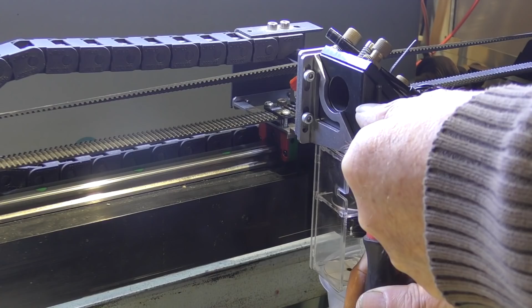Now what we've got to do is move the beam backwards. And how do we do that? Well, the answer is quite simple. If we look at it from this point of view, the beam is coming down here. I'll exaggerate, it's way off centre, it's too far forward. If we want the beam to come further down the mirror, in other words, we want it to finish up here, look, what we've got to do, we've got to raise the head up to make the beam hit the mirror in here lower down. So I've got to raise this mirror up now, and as I raise it up, so I shall actually be moving the beam backwards.